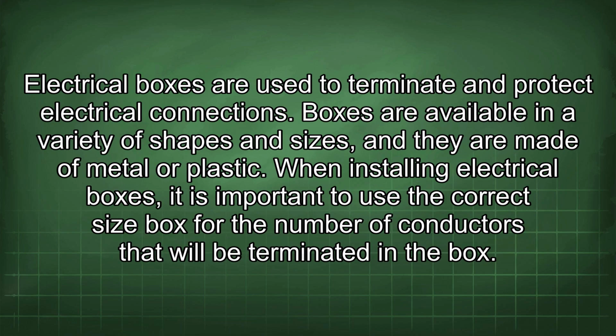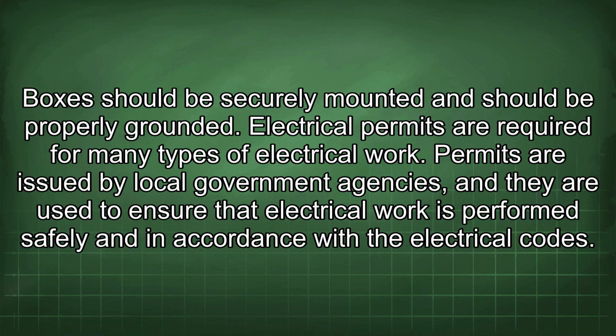Electrical boxes are used to terminate and protect electrical connections. Boxes are available in a variety of shapes and sizes, and they are made of metal or plastic. When installing electrical boxes, it is important to use the correct size box for the number of conductors that will be terminated in the box. Boxes should be securely mounted and should be properly grounded.